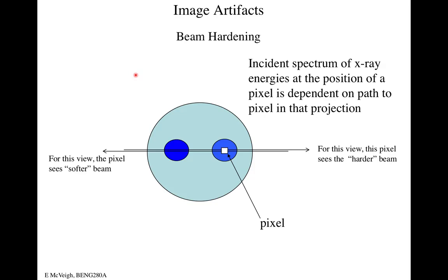And the reason was we filtered those out with a piece of copper or aluminum such that those low energy photons didn't hit the patient, right? Some of the filtering is naturally done by the target itself and some by the glass, etc. But then we put a copper filter in front of it. So in a way, what we've done there is we have taken the average energy of the X-rays that were created at the target, and we've increased the average energy of the beam coming out by getting rid of the low energy photons, right? The patient also does that.